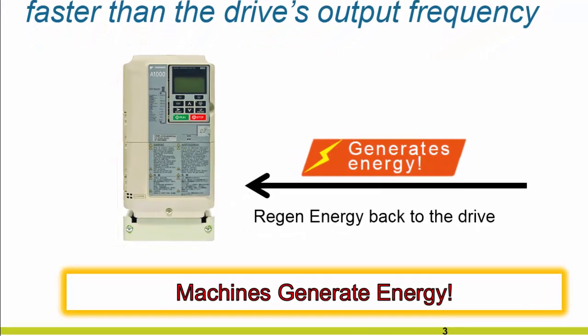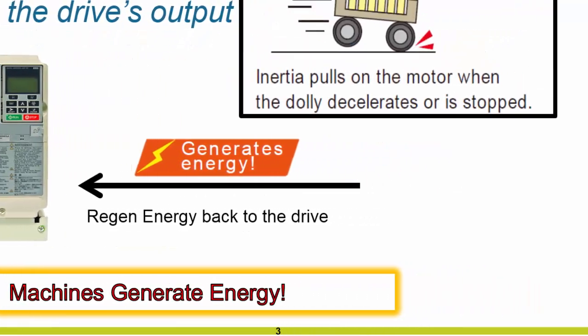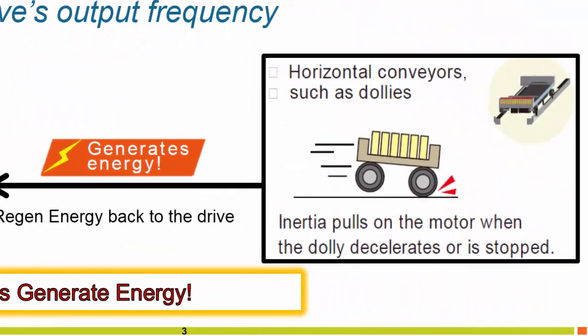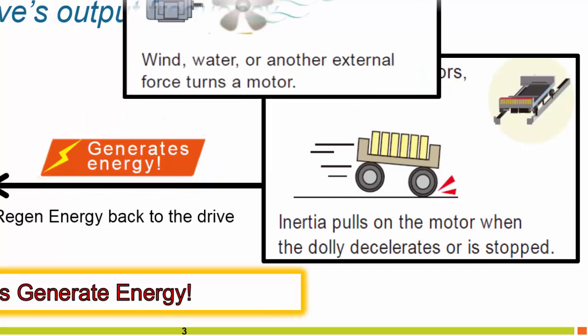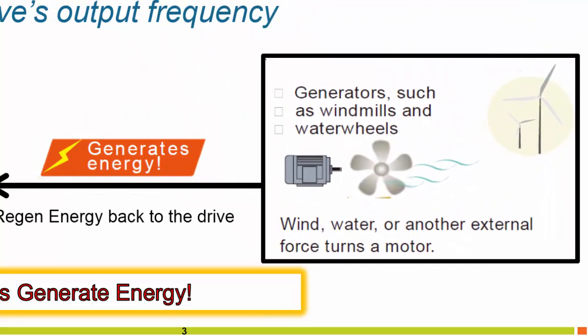For example, conveyors, or applications with high-inertial loads. When we slow this down or we stop that load, it regenerates energy. Even variable torque loads, such as fans or pumps, can have external forces turning the motor resulting in regenerative energy.